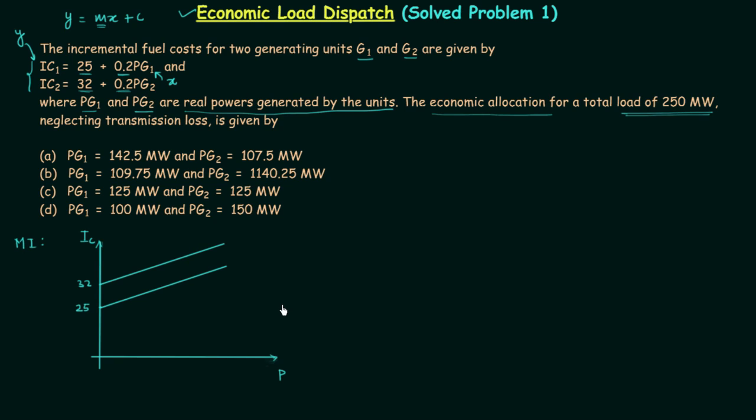So in this way you can easily obtain the characteristics for generator G2 and generator G1. And using this we will try to find out the correct option. In the last lecture I told you we perform the loading based on the incremental cost. The generator having the least incremental cost is loaded more. And in this case, if you compare G1 and G2, you will find G1 is having the less incremental cost. So we will load G1 more, and using this information we will try to find out the correct option.